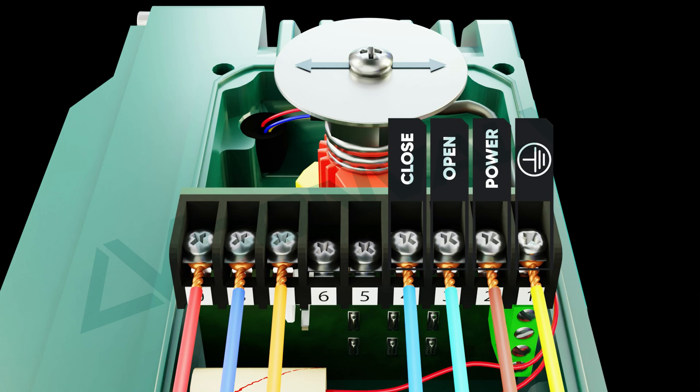To rotate or close the actuator in the clockwise direction, apply power to terminal 2 and terminal 4. The actuator will rotate clockwise until it reaches the internal limit switch and then shuts off.